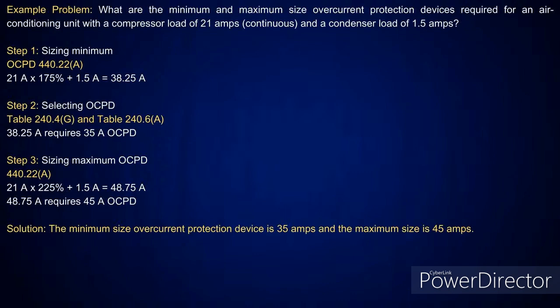I've got a minimum and maximum size rating that was on that HVAC equipment. And what was that based on? It was based on the percentages in the code. All right. Now, this brings up an interesting point too. Let's just say you have a 21 amp full load current, and you say, I'll use a number 12. You should be covered, and then you put it on a 40 amp breaker. It's code compliant from the minimum, but if worst comes to worst, that AC unit might give you permission to use, like, a number 10. I've even seen them do a number 12 to a 50 or a number 10 to a 50 or whatever.